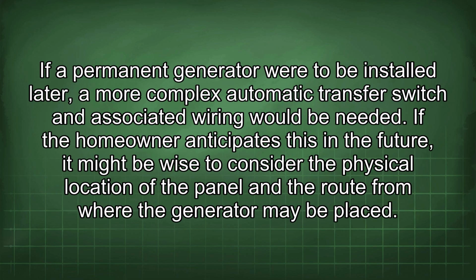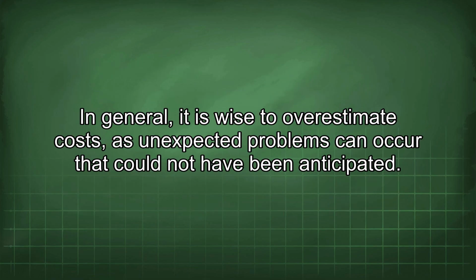If a permanent generator were to be installed later, a more complex automatic transfer switch and associated wiring would be needed. If the homeowner anticipates this in the future, it might be wise to consider the physical location of the panel and the route from where the generator may be placed. In general, it is wise to overestimate costs, as unexpected problems can occur that could not have been anticipated.